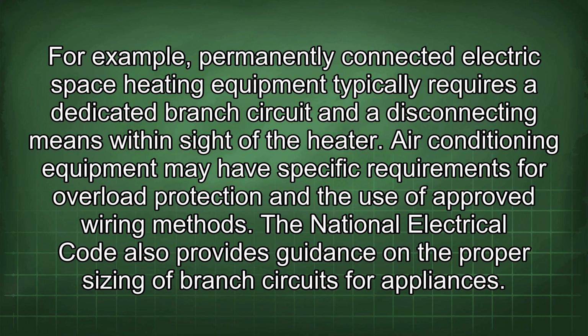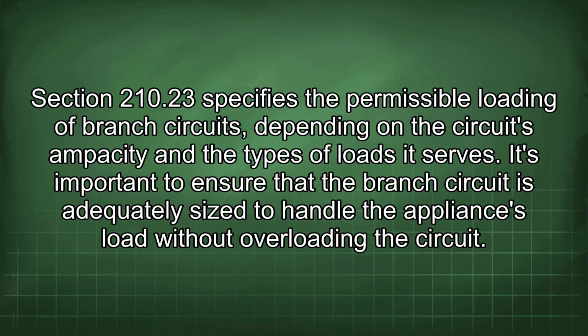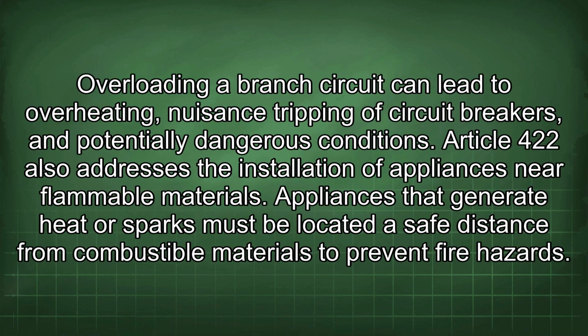The National Electrical Code also provides guidance on the proper sizing of branch circuits for appliances. Section 210.23 specifies the permissible loading of branch circuits, depending on the circuit's ampacity and the types of loads it serves. It's important to ensure that the branch circuit is adequately sized to handle the appliance's load without overloading the circuit. Overloading a branch circuit can lead to overheating, nuisance tripping of circuit breakers, and potentially dangerous conditions.